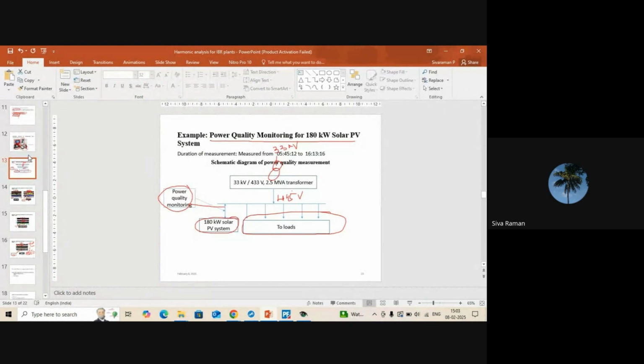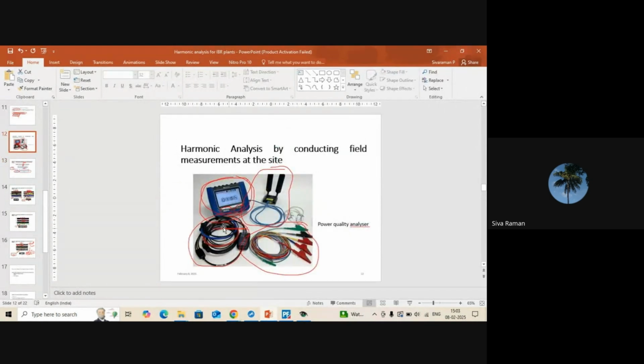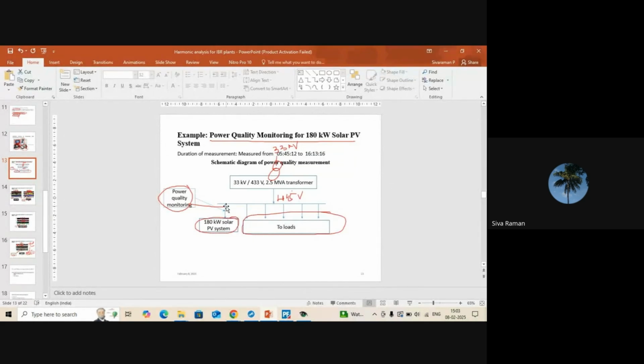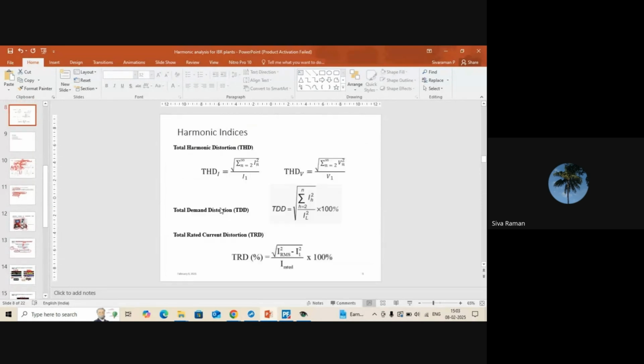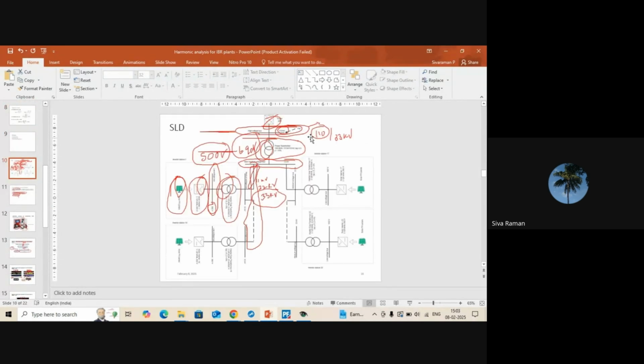For the power quality measurement, the analyzer and the accessories, current transformers, voltage PTs and cables, we have to connect at the point where we want to measure the harmonics. For example, for this power plant, the 110 kV voltage is the point of connection. In this location only, we have to complete the harmonic measurement. So we have to connect the power quality analyzer at this location.